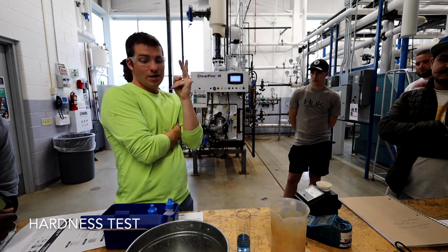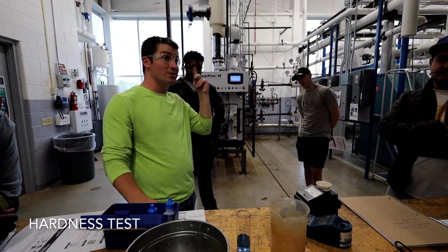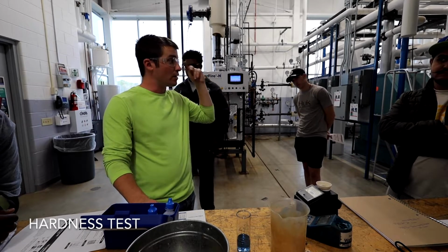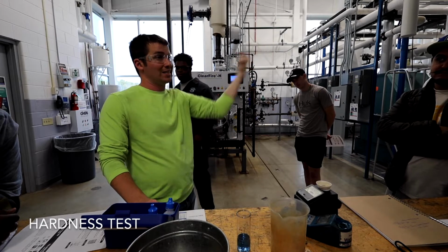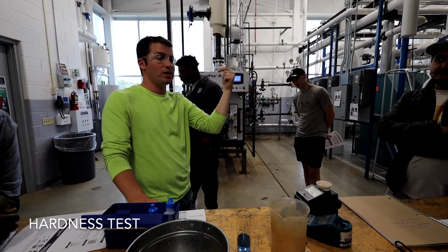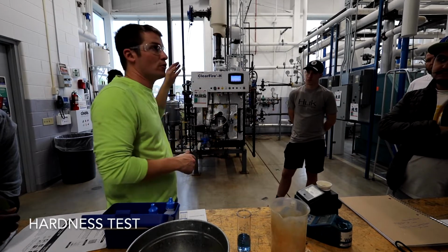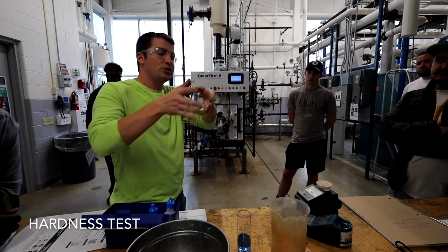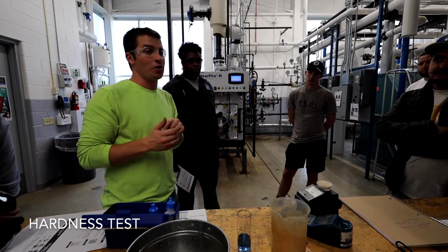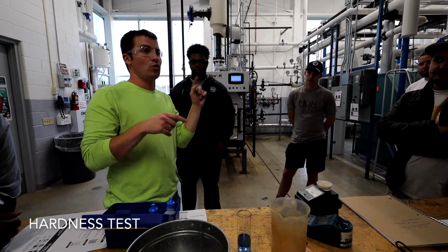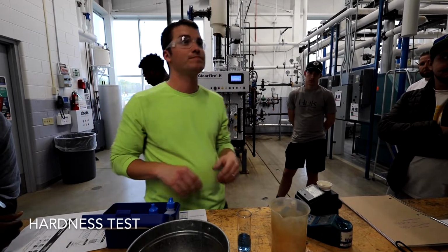So you know, because your feed water had elevated hardness, it's got to either be your condensate that's causing the issue. Maybe you have a contamination, right? You have a heat exchanger in the plant that's leaking and you're getting hot water on the other side leaking back in, and that might have elevated hardness compared to what we want in our boiler. Or again, hey, my softener or my RO or something of my pre-treatment is not working as it should, right? So this would spin me into, okay, I need to dig into what's not working out of the softener and the condensate and try to figure that out. That's what we got going.